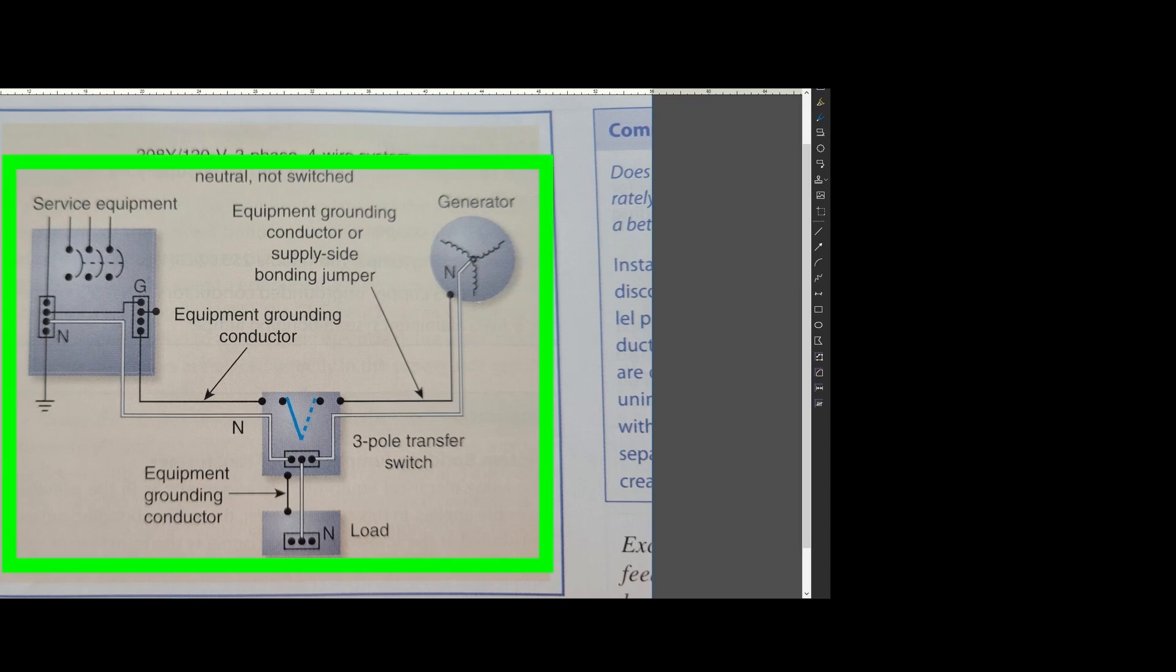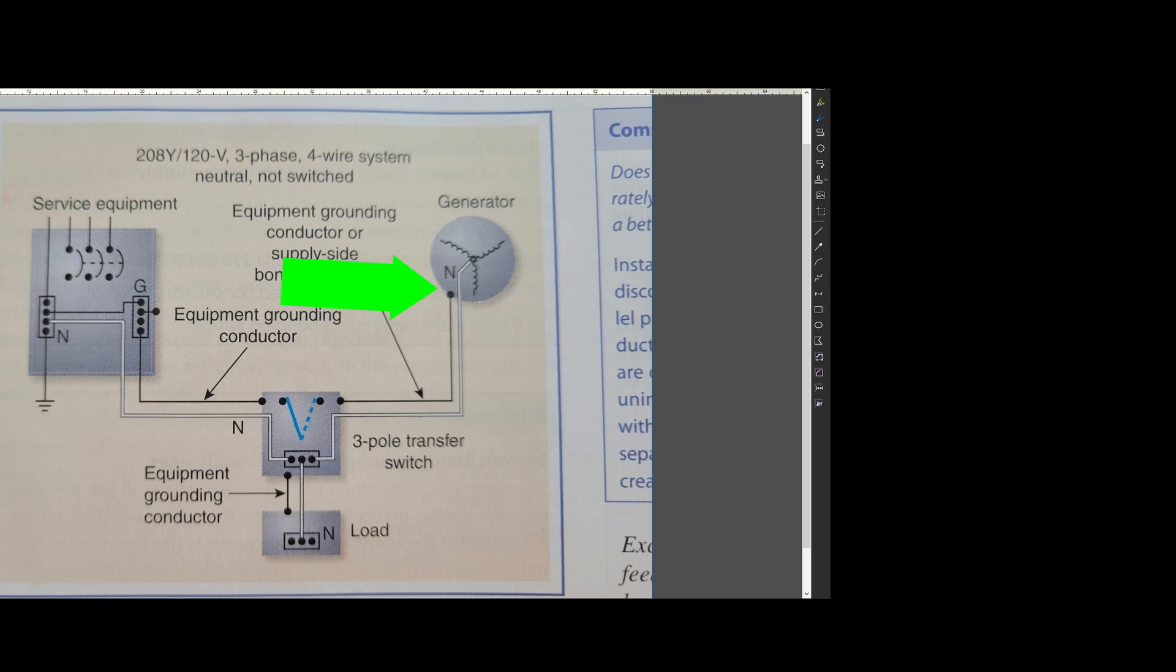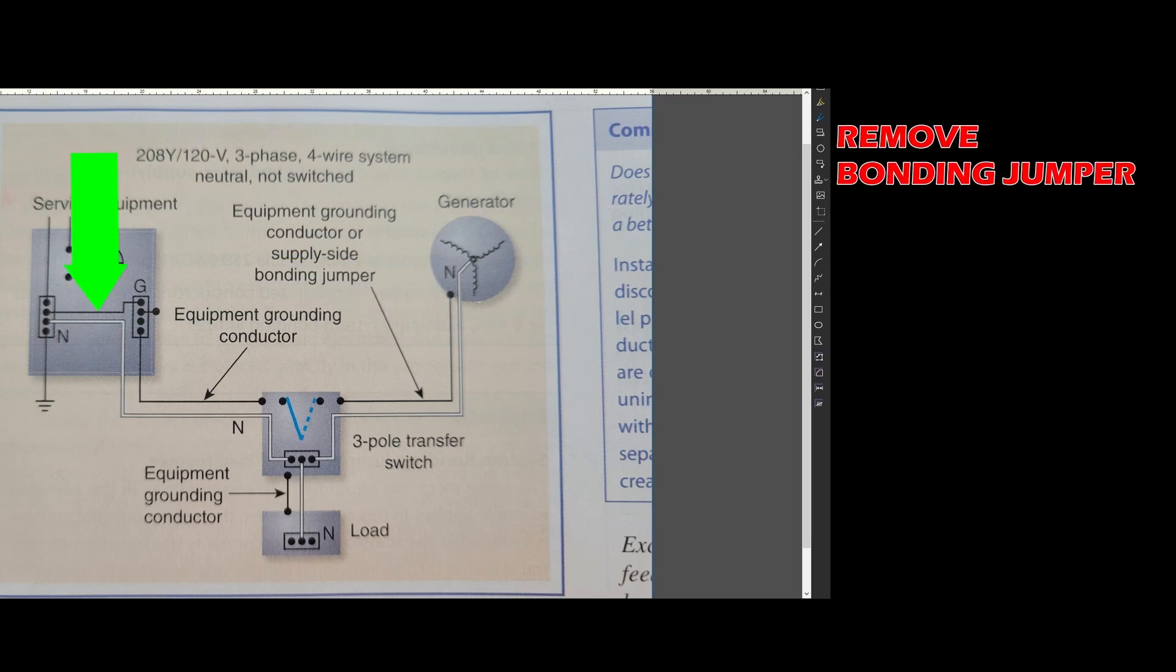So the neutral to ground bonding jumper at your generator will need to be removed because your electrical panel already has this installed here. By code, only one bonding jumper is allowed per electrical system.